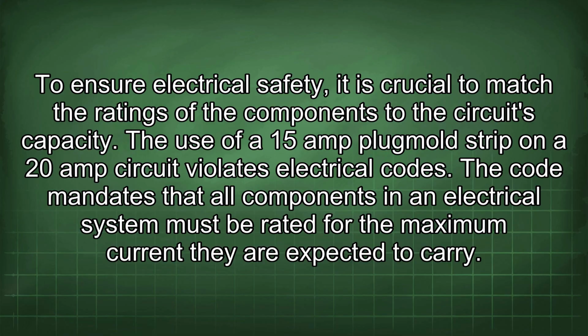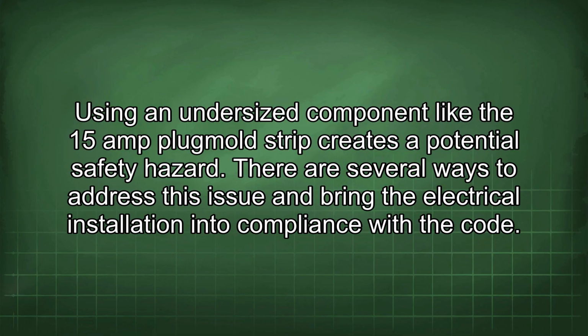The use of a 15 amp Plugmold strip on a 20 amp circuit violates electrical codes. The code mandates that all components in an electrical system must be rated for the maximum current they are expected to carry. Using an undersized component like the 15 amp Plugmold strip creates a potential safety hazard. There are several ways to address this issue and bring the electrical installation into compliance with the code.